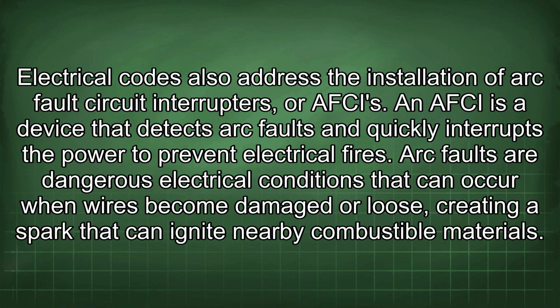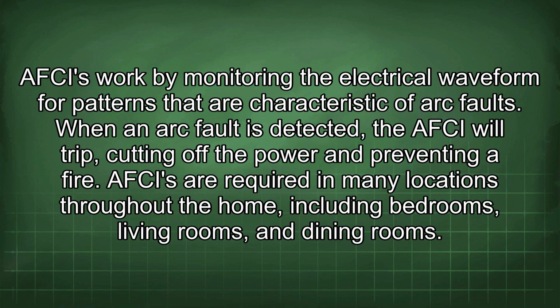Electrical codes also address the installation of arc fault circuit interrupters, or AFCIs. An AFCI is a device that detects arc faults and quickly interrupts the power to prevent electrical fires. Arc faults are dangerous electrical conditions that can occur when wires become damaged or loose, creating a spark that can ignite nearby combustible materials. AFCIs work by monitoring the electrical waveform for patterns that are characteristic of arc faults. When an arc fault is detected, the AFCI will trip, cutting off the power and preventing a fire. AFCIs are required in many locations throughout the home, including bedrooms, living rooms, and dining rooms.